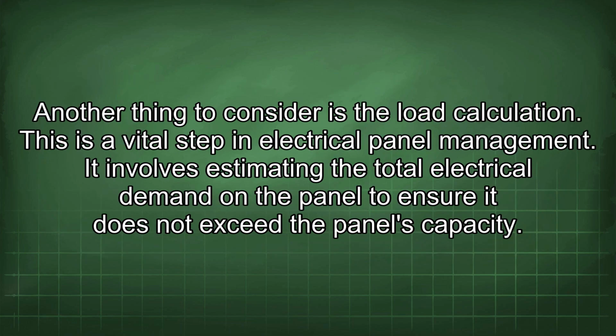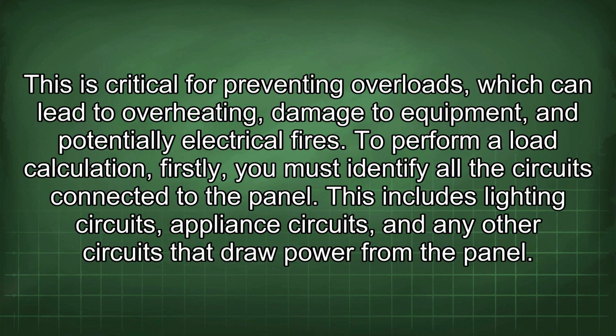Another thing to consider is the load calculation. This is a vital step in electrical panel management. It involves estimating the total electrical demand on the panel to ensure it does not exceed the panel's capacity. This is critical for preventing overloads, which can lead to overheating, damage to equipment, and potentially electrical fires. To perform a load calculation, firstly, you must identify all the circuits connected to the panel.